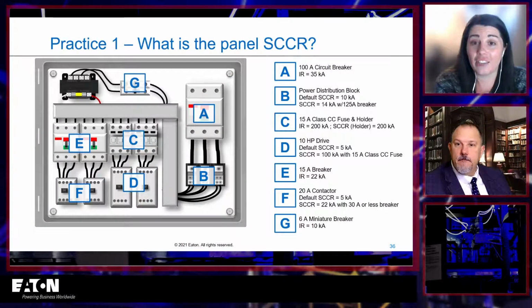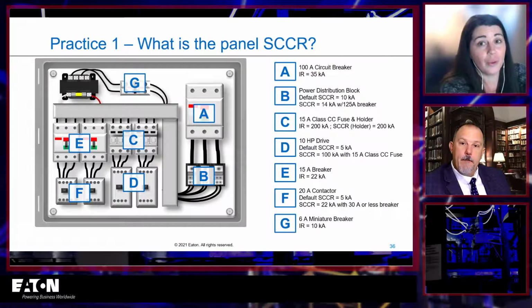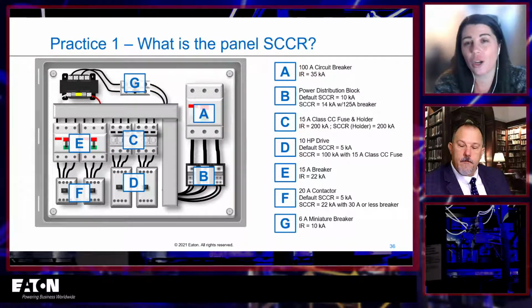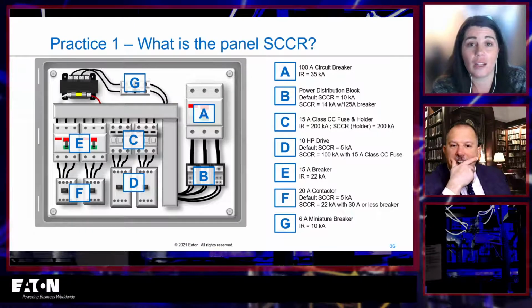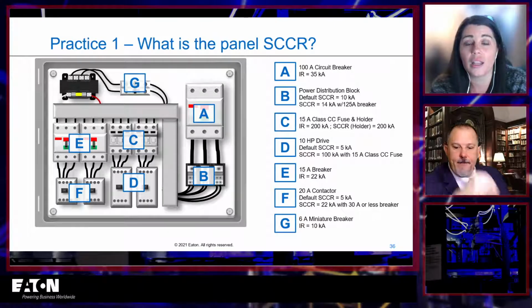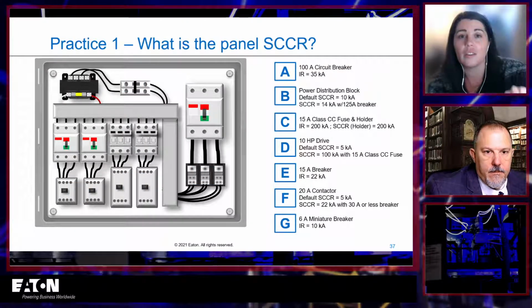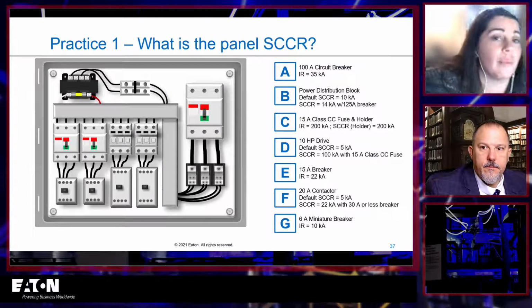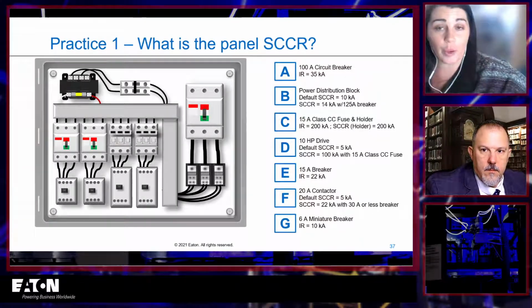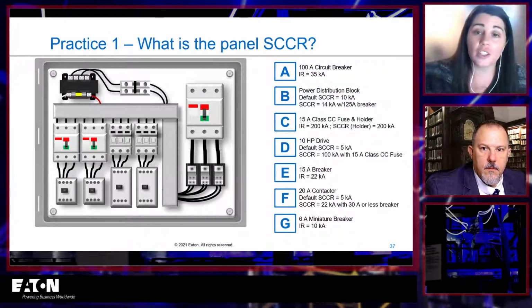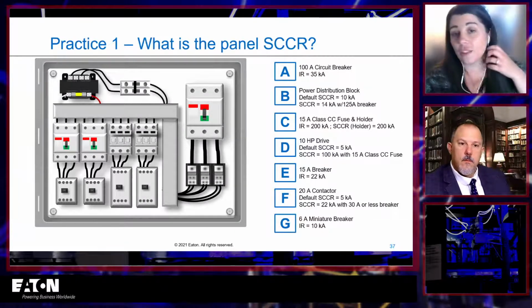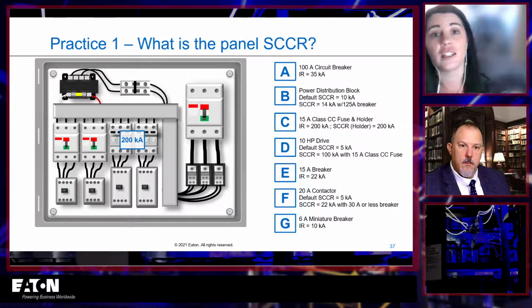All right, I actually have an example here for us that we can go through for calculating panel SCCR. We don't have a current limiting main here, so we're not using that other step to help us through. We can look at each of these pieces of equipment here, and if you click, now we can see, pay attention to where these were marked because it does take away their labels. We're going to start because UL 508A tells me to start with determining my branch short circuit current ratings, right? So to determine my branch short circuit current ratings, I have to look at each of those.